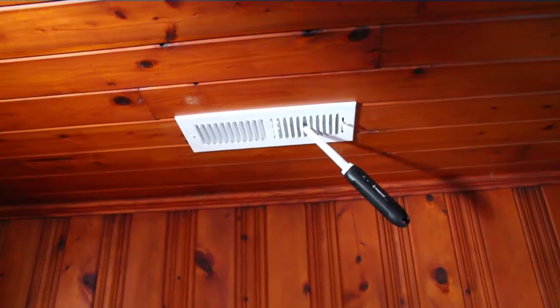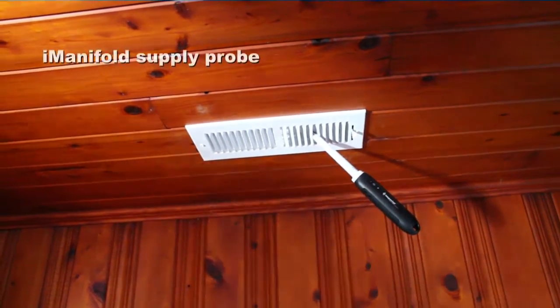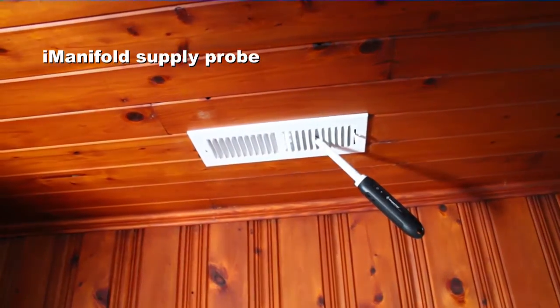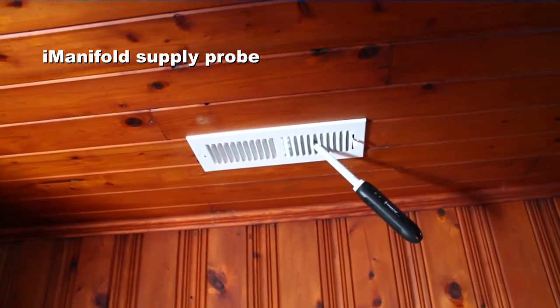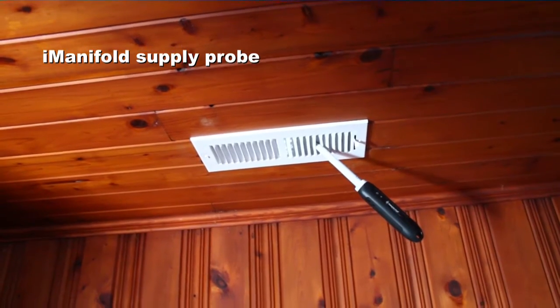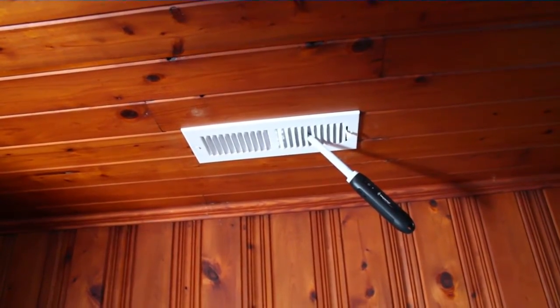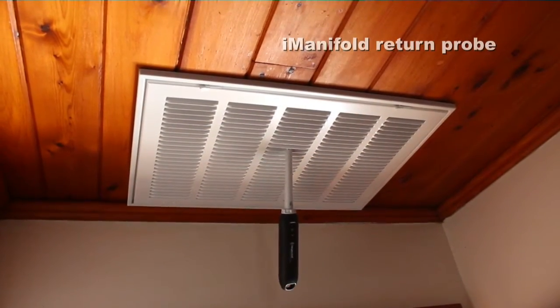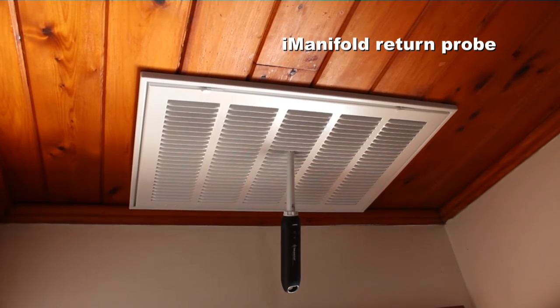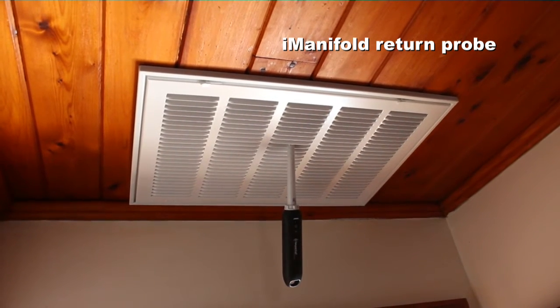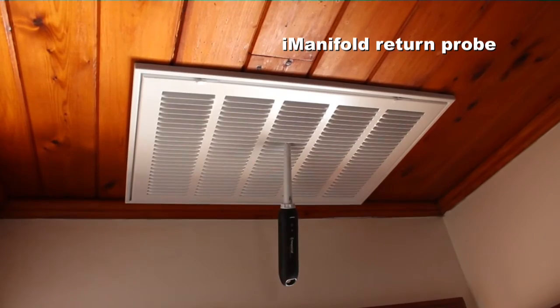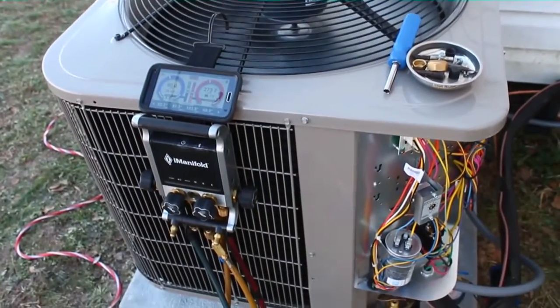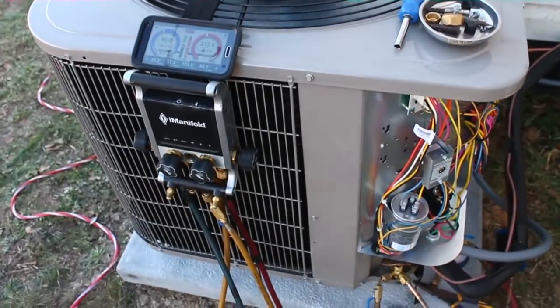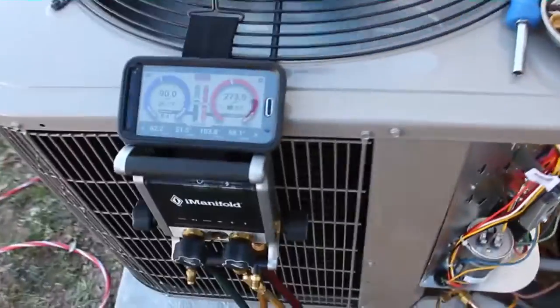I had the supply probe put into one of the outlets that first come off of the duct system. It gets a lot of good airflow, so it's almost like putting it right at the air handler. It's a good sense of supply air. This is my return probe in one of the return grills. There are 2 grills. I'm using this one, although there might be a little temperature variation between the 2. It shouldn't be very much. We have been running for about, I don't know, 10 or 15 minutes. I don't really remember. We're in the right ballpark.